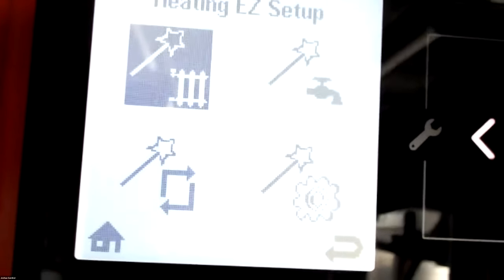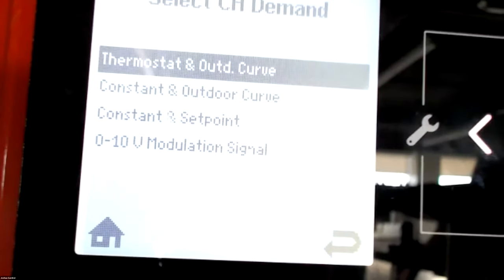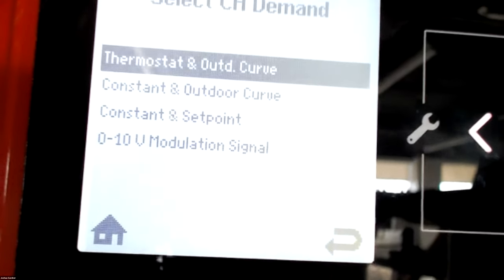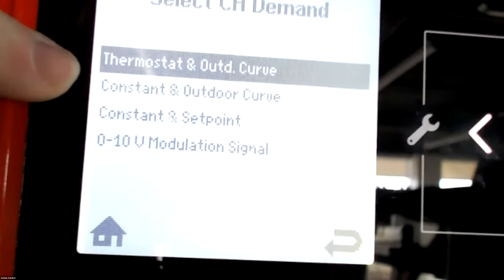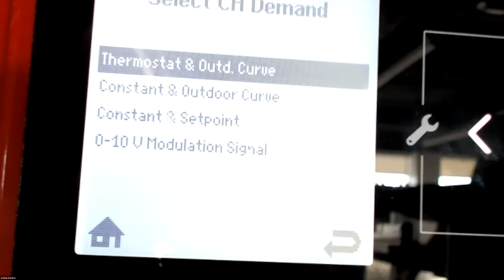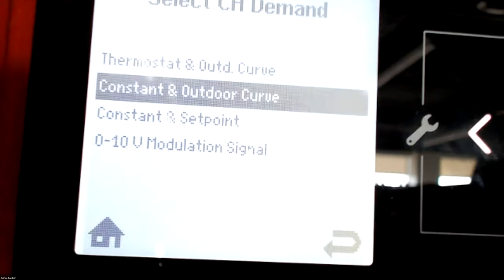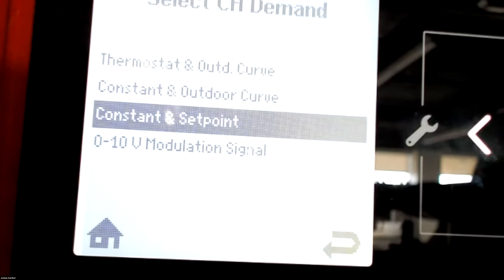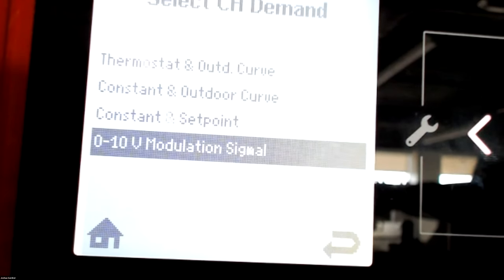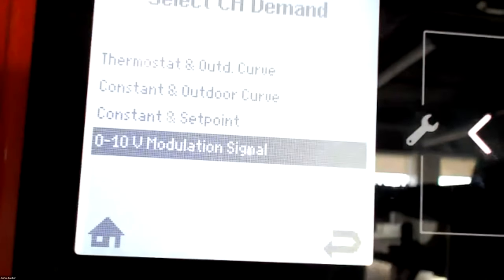So we start at heating easy setup. We have the outdoor sensor installed. So we have options here for thermostat and outdoor curve, constant and outdoor curve, constant and set point, and 0 to 10 modulation. 0 to 10 modulation is we have up on our low voltage connection, the modulation signal. We'll click that and that's it. You'll set up everything in your auxiliary control. That's all you need to do if you're going to be using modulation.